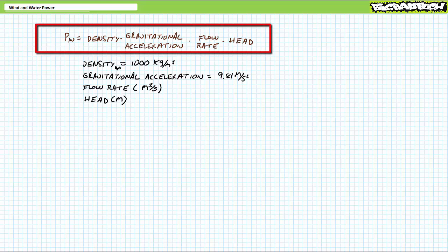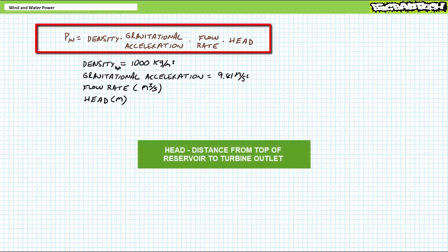One method of determining input power to a hydropower turbine demonstrates input power is density in kilograms per meter cubed, times gravitational acceleration in meters per second squared, times head, the distance from the top of the reservoir to the outlet in meters, times a flow rate in cubic meters per second.